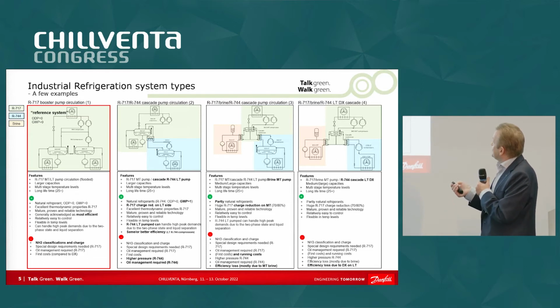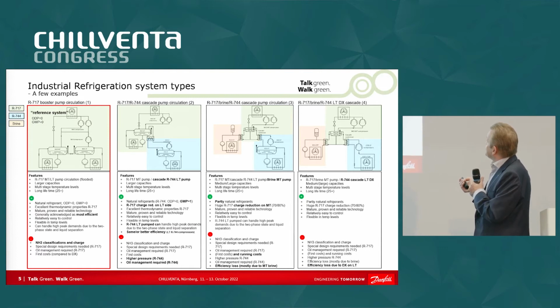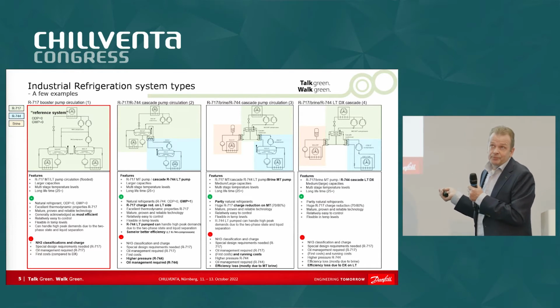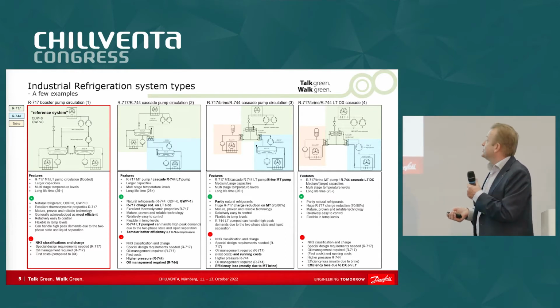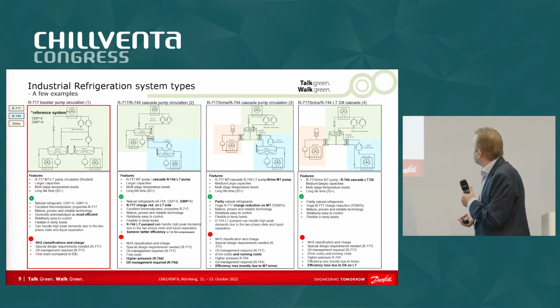Then we have another one. It looks the same, but this part is changed by this one. And that's a DX system. And that we often see if the capacity here is low and it doesn't justify the cost of a flooded system here. So that's another way of doing it. And of course, because you run with DX, there's superheat. And superheat means that you need to have a lower suction pressure. And then the efficiency gets lower. Okay.